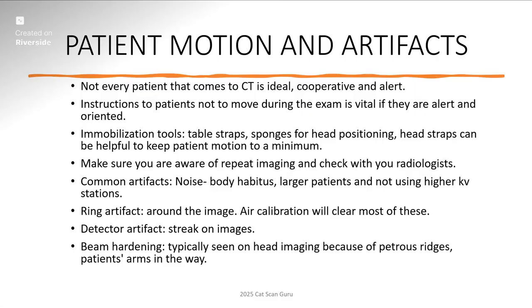Now we also come into contact with ring artifacts. So you'll see this nice little ring around your image, which you're like, okay, why is there a ring artifact? Now, 9 times out of 10, if you do an air calibration test and make sure nothing is in the field of where the X-ray tube is, it will clear up some of these. What I've found is that one time at a hospital I worked at many years ago, the tech who would do the phantoms every morning would leave the phantom inside the gantry as the air cal was going on. Well, all of a sudden we get a bunch of ring artifacts and the radiologist is like, okay, we got to figure this out.